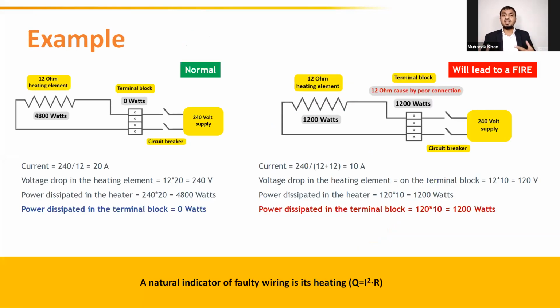Let us take a very simple example, broken down, of how a loose connection can convert into heat. In this example, we have taken a 240 volt power supply supplying a 12 ohm heating element through a circuit breaker and a terminal block. Under normal conditions, the contact resistance at the circuit breaker contact is 0. The contact resistance at the terminal block is 0. So we have only one resistance in the loop, and that is the resistance of the heating element, which is 12 ohms. If we apply Ohm's law, around 4,800 watts of energy coming out of the power supply unit will be dissipated on the heating element, right?